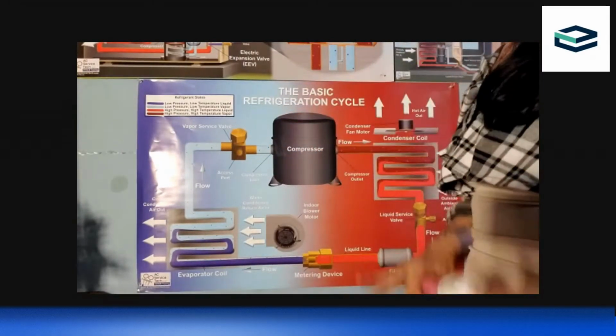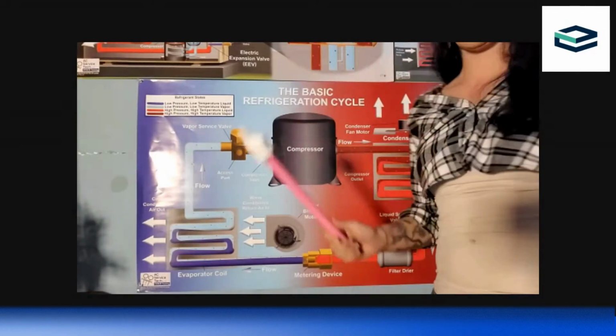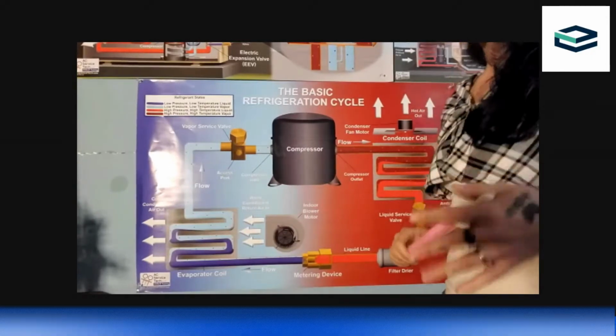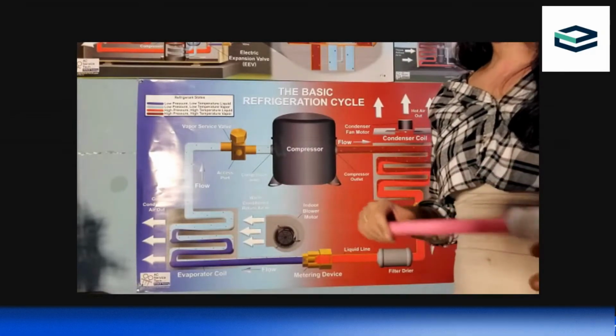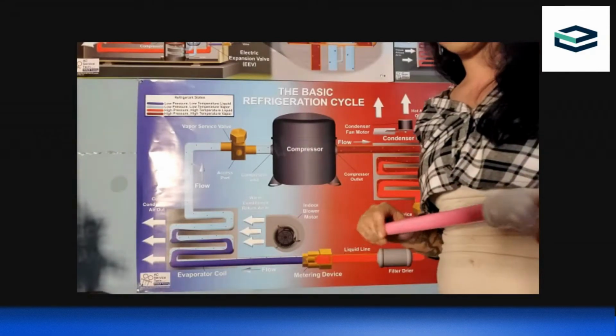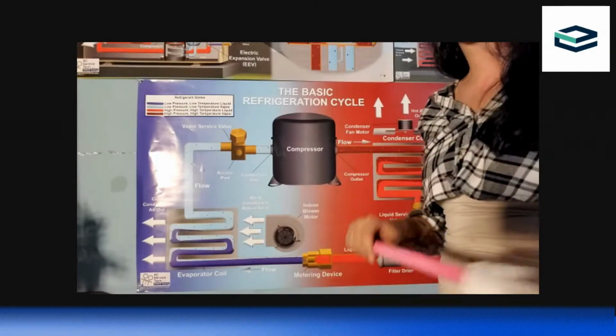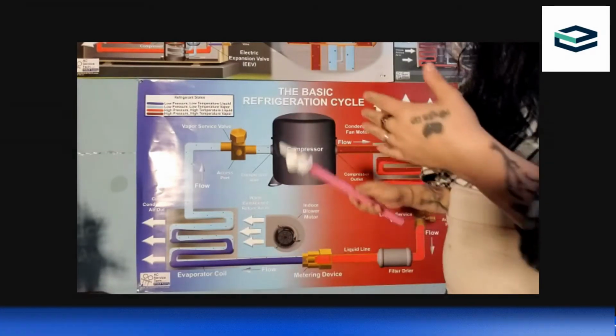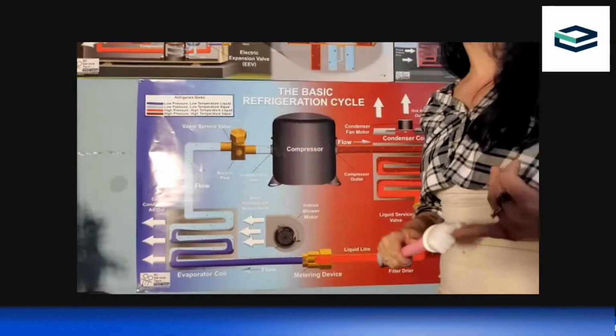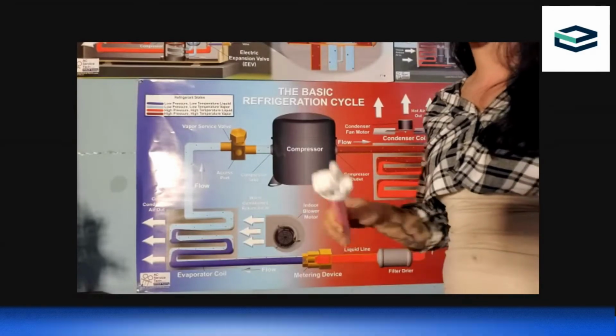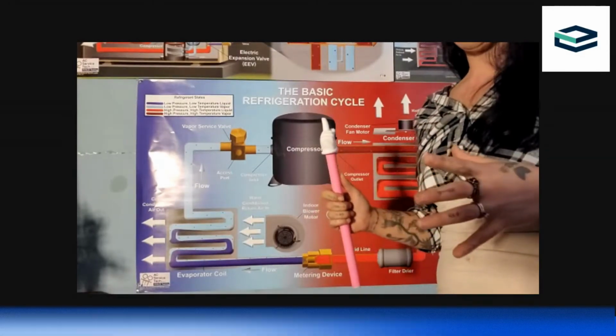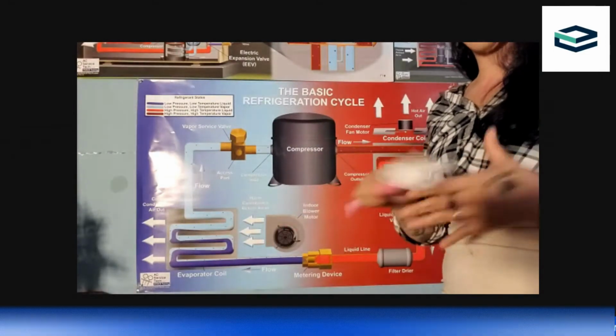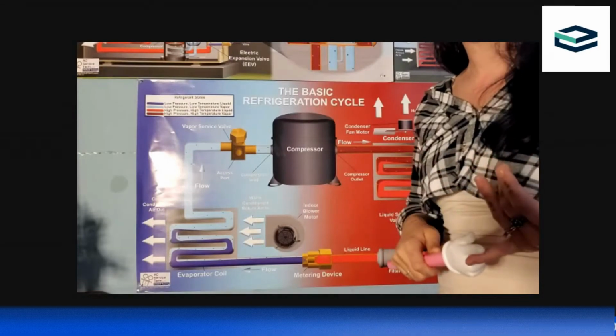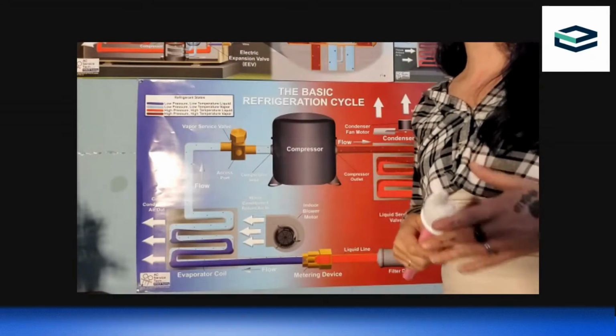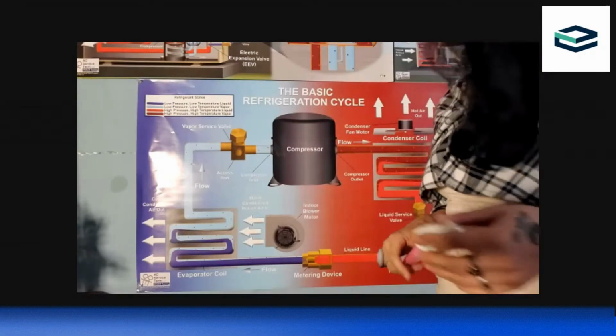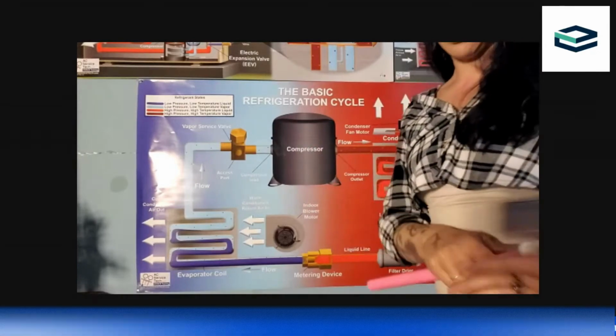For this, there are so many refrigerants out there, you guys, and I could never cover them in this amount of time. So for all intents and purposes today, I'm going to talk about 410A and R22. R22 is actually a banned substance already. 410A is on its way as well as we switch to A2L refrigerants, which we'll talk about a little bit at the end. But the majority of the systems that you see, some of them still have R22 in them. That's 100% legal. You don't have to rip out every system when a refrigerant goes out and is blacklisted, but we do have to think about replacing them if they get a leak. You would learn about this in the EPA course if you do decide to take that. SkillCat does offer it.